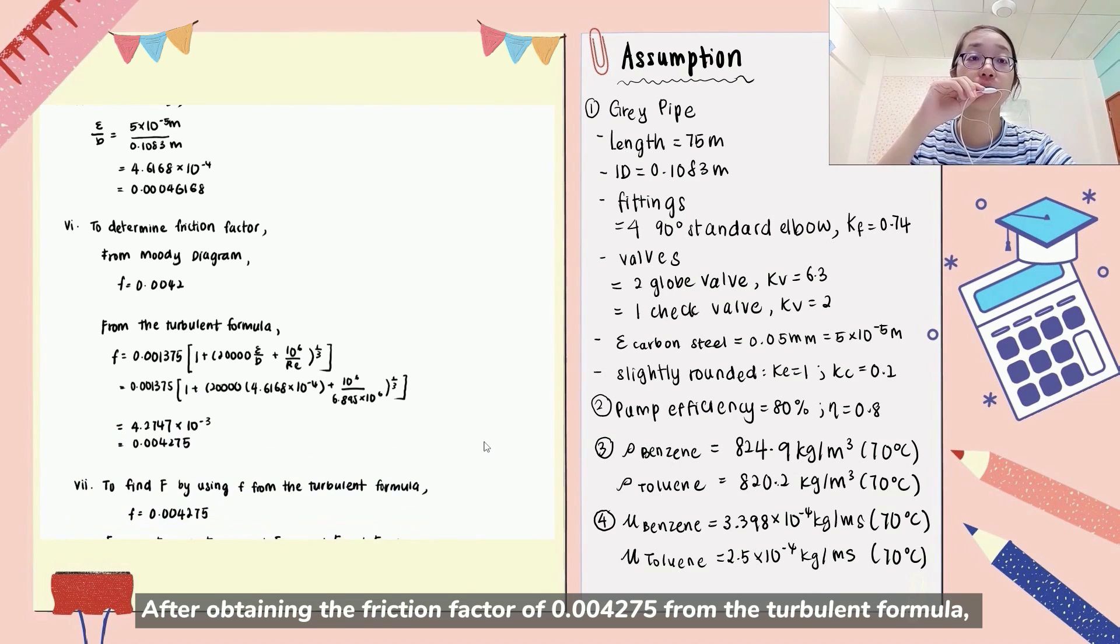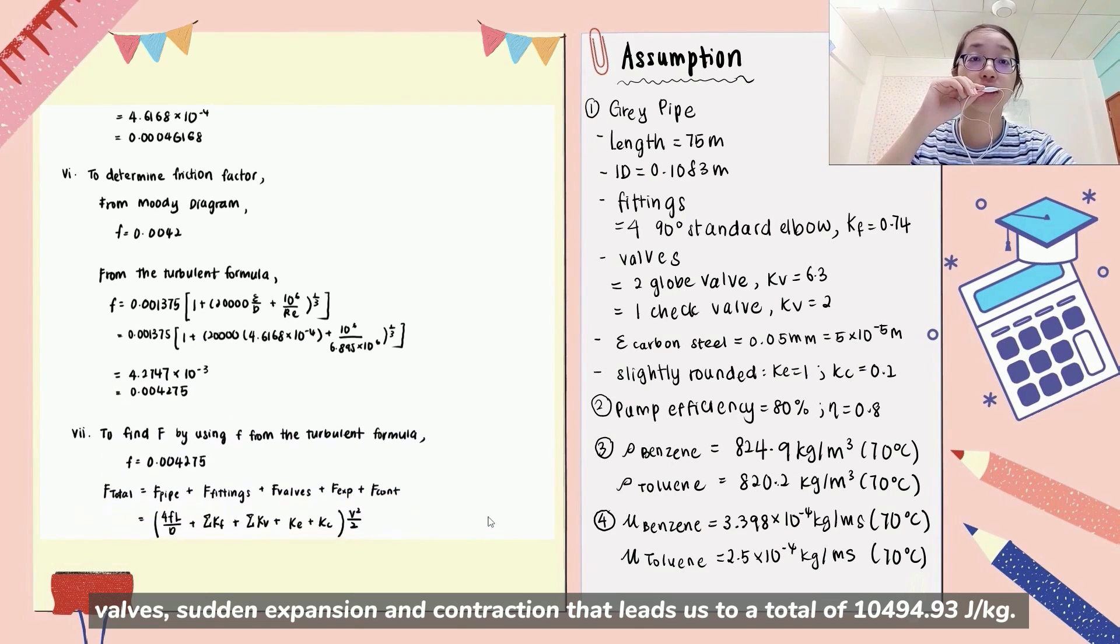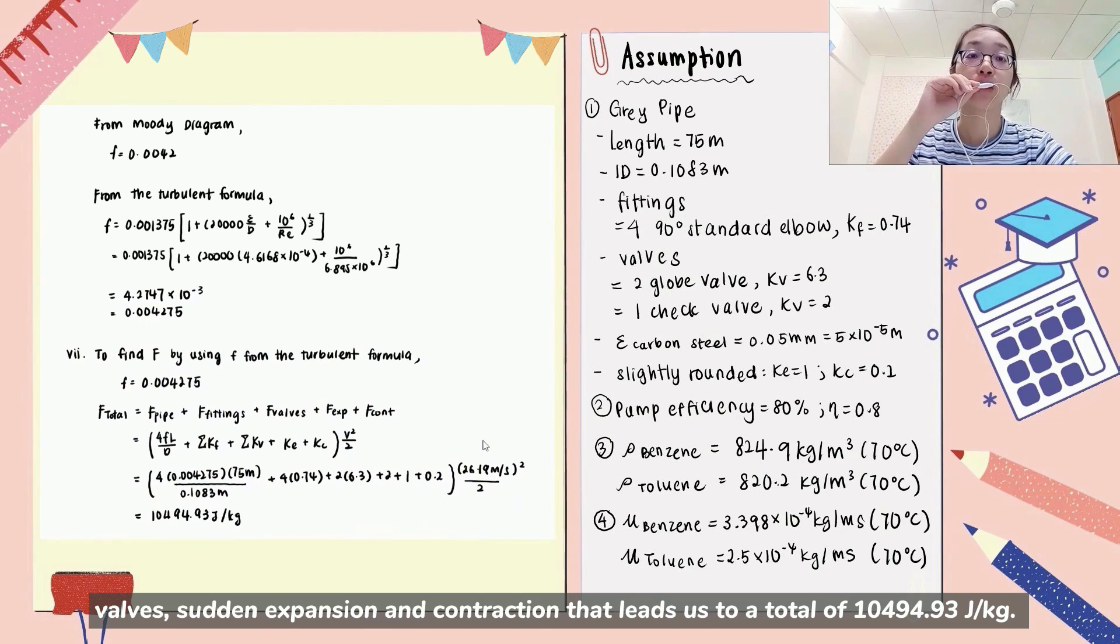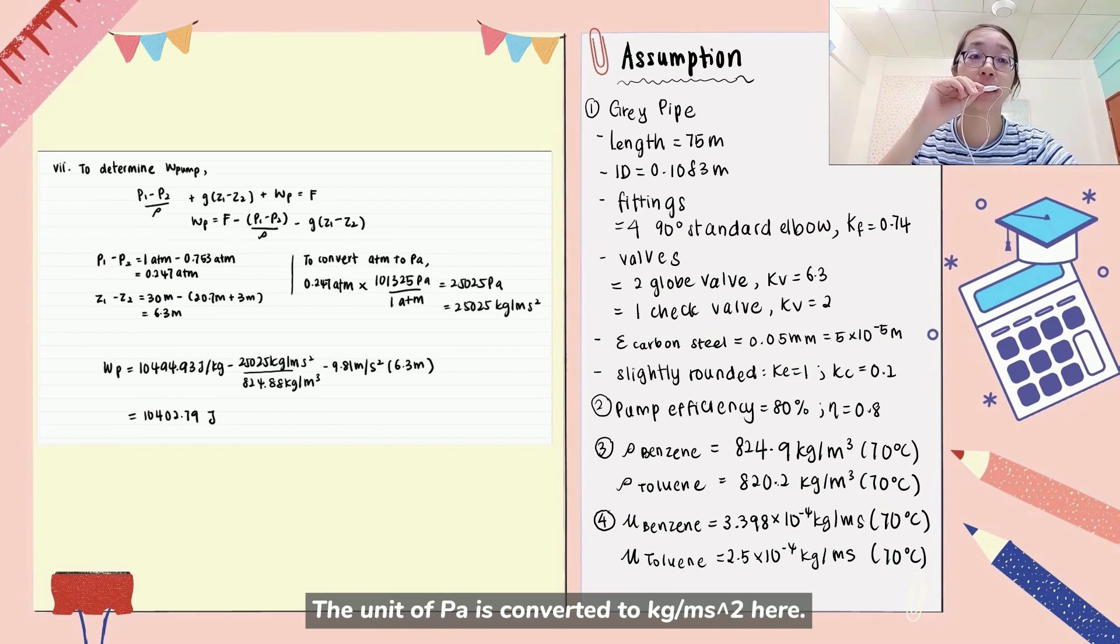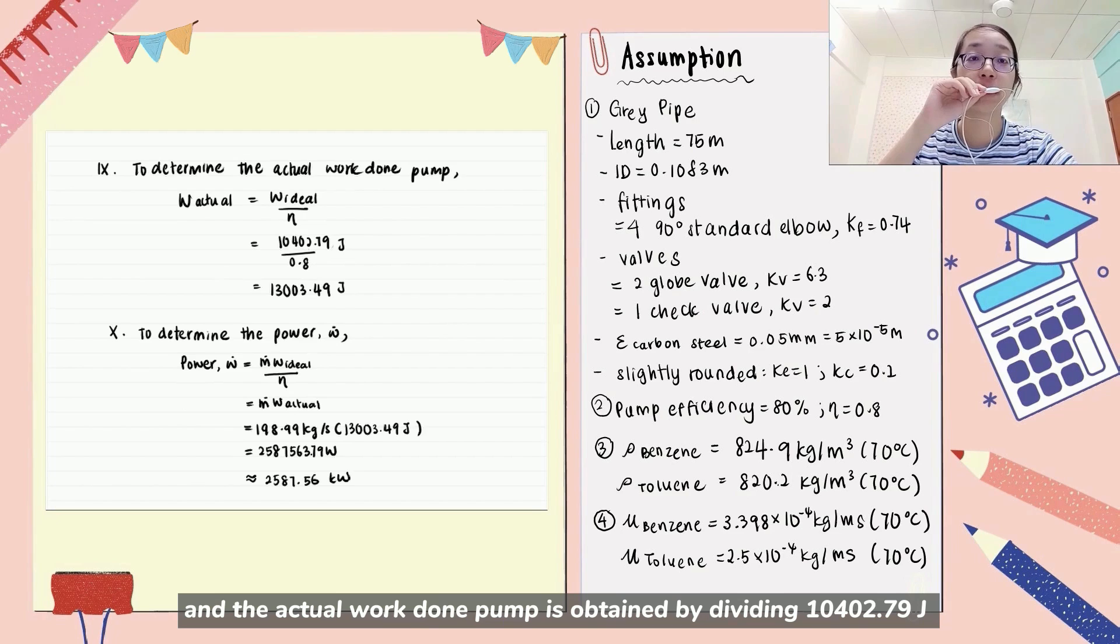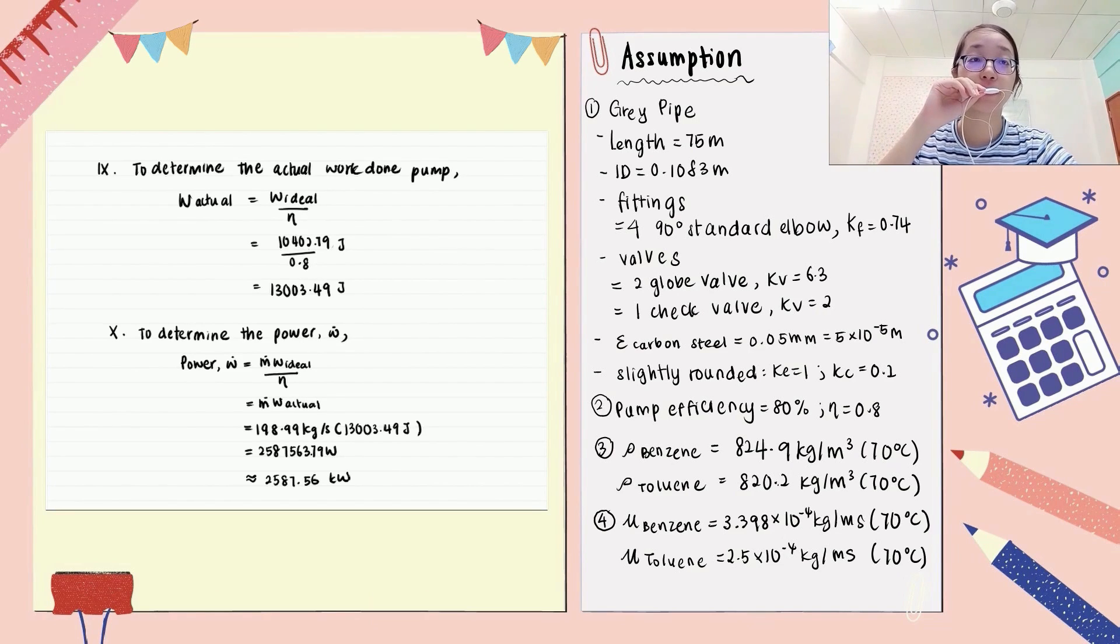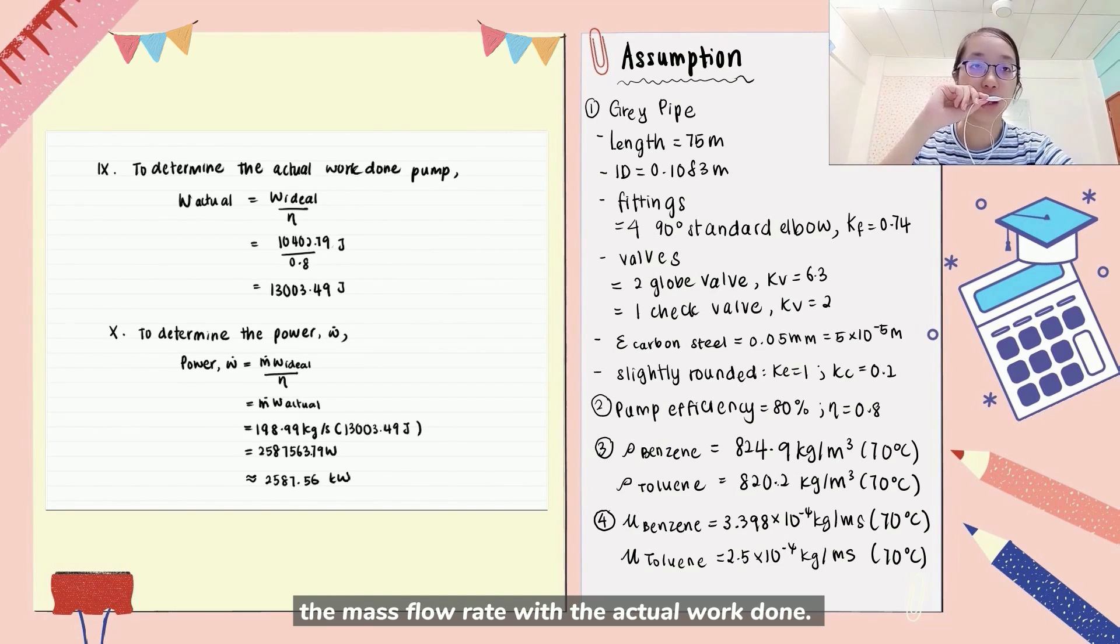After obtaining the friction factor of 0.004275 from the turbulent formula, we can apply in the total friction by adding up the friction of pipe, fittings, valves, sudden expansion and contraction that lead us to a total of 10494.93 Joules per kg. The unit of Pascal is converted to kg per meter second square here. To determine the work of pump, simplified Bernoulli equation is used and the actual work of pump is calculated by dividing 10402.79 Joules with the pump efficiency of 0.8. Lastly, the power of 2587.56 kW can be determined by multiplying the mass flow rate by using the actual work.